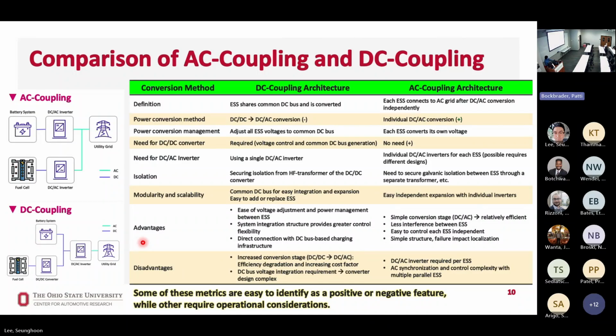In the DC coupling approach, multiple ESS units share a common DC bus and use a single DC to AC inverter. This allows for centralized voltage regulation and power flow management at the DC level, improving overall conversion efficiency. The common DC bus also enhances modularity, making it easier to add or replace energy storage units. However, DC coupling typically requires DC to DC converters for voltage matching, and additional conversion stages may introduce efficiency losses.